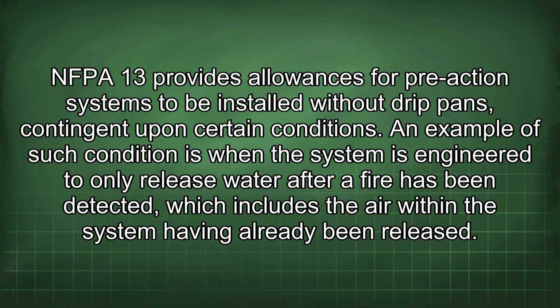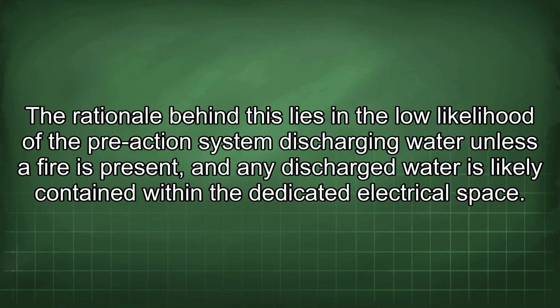An example of such a condition is when the system is engineered to only release water after a fire has been detected, which includes the air within the system having already been released. The rationale behind this lies in the low likelihood of the pre-action system discharging water unless a fire is present, and any discharged water is likely contained within the dedicated electrical space.